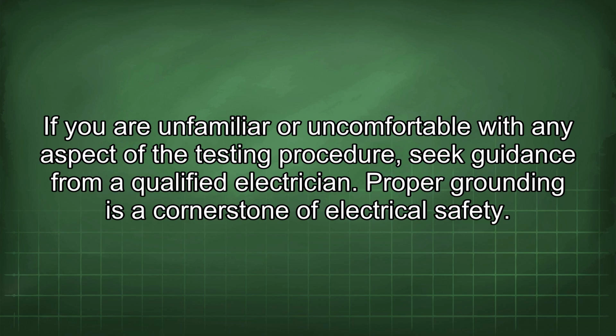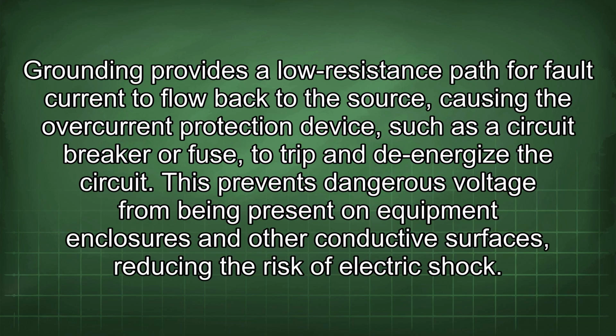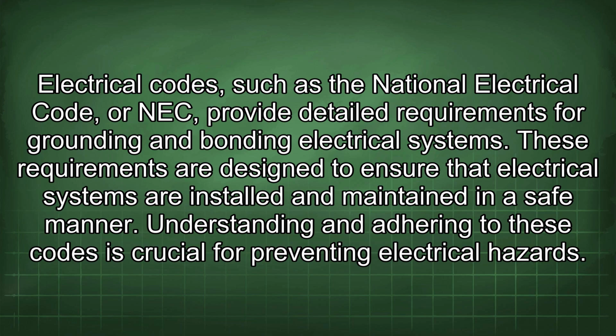Proper grounding is a cornerstone of electrical safety. Grounding provides a low resistance path for fault current to flow back to the source, causing the overcurrent protection device, such as the circuit breaker or fuse, to trip and de-energize the circuit. This prevents dangerous voltage from being present on equipment enclosures and other conductive surfaces, reducing the risk of electric shock. Electrical codes, such as the National Electrical Code, or NEC, provide detailed requirements for grounding and bonding electrical systems. These requirements are designed to ensure that electrical systems are installed and maintained in a safe manner. Understanding and adhering to these codes is crucial for preventing electrical hazards.